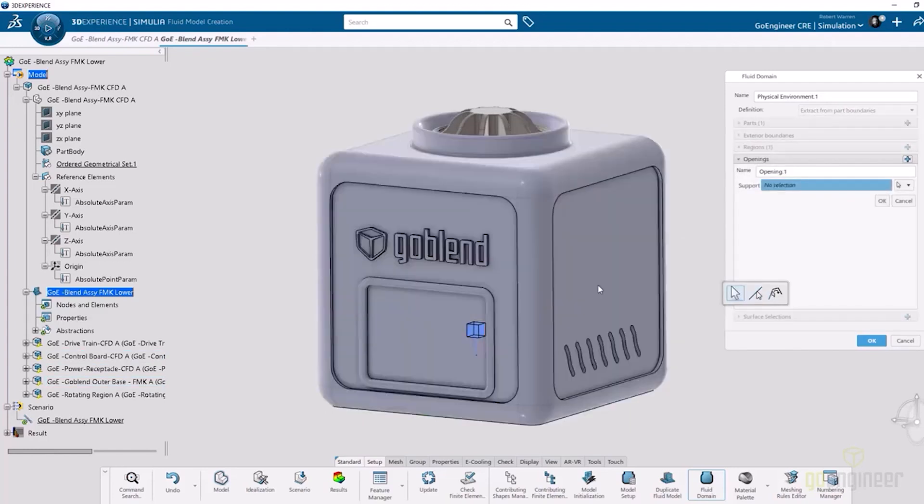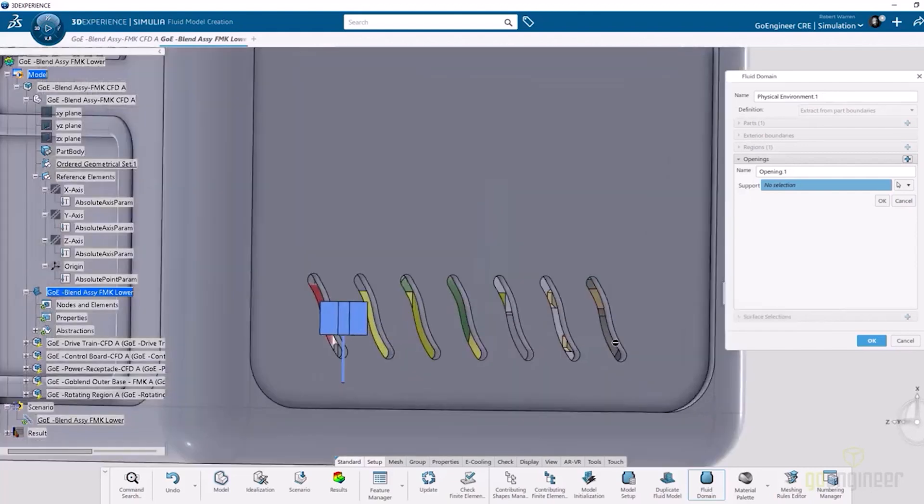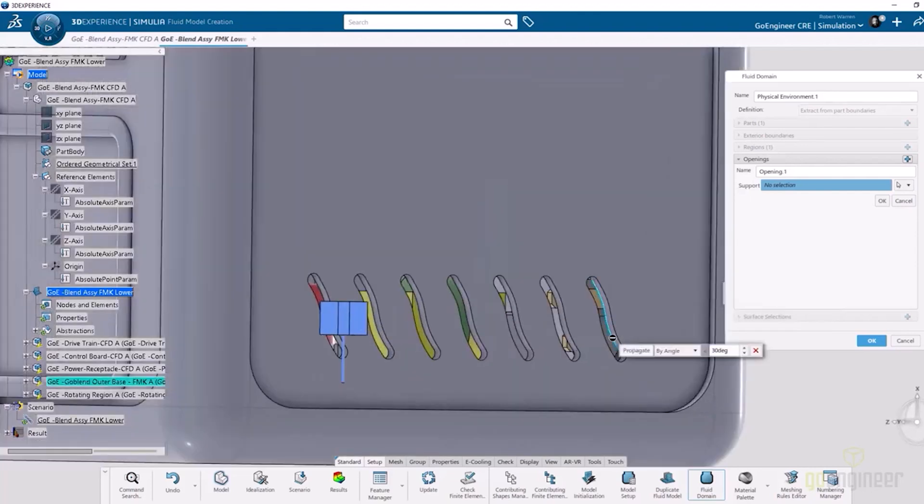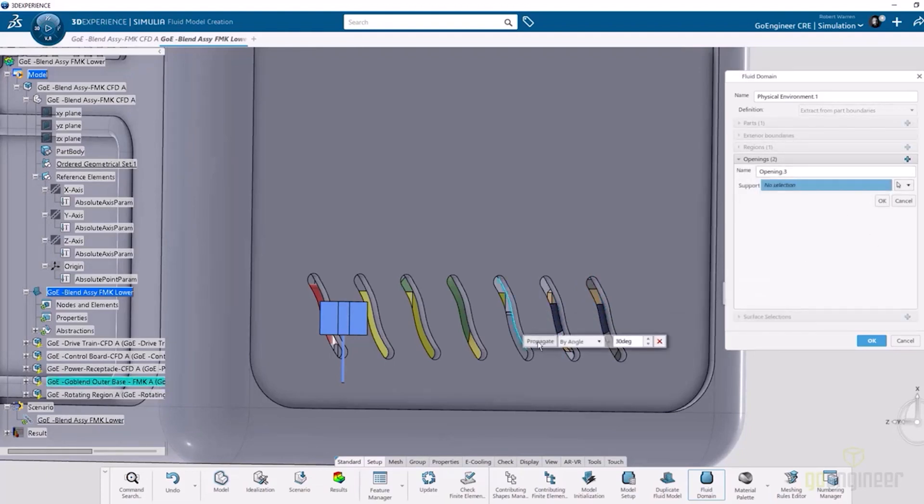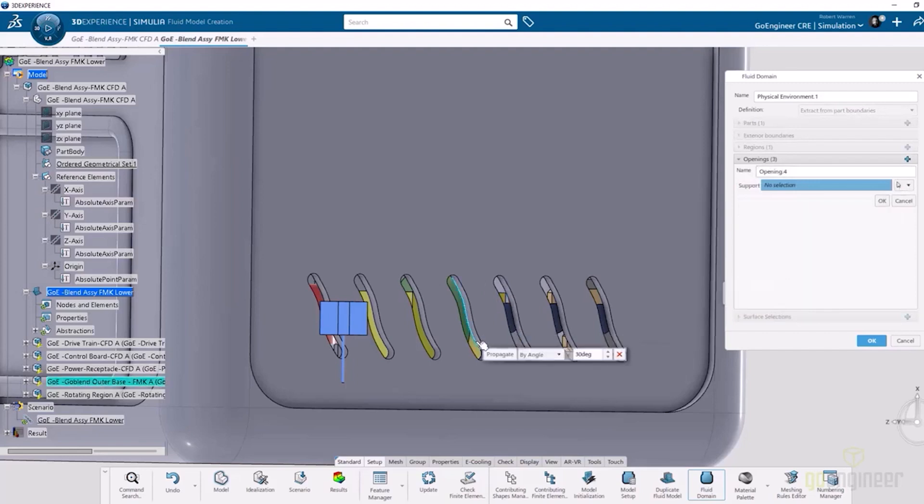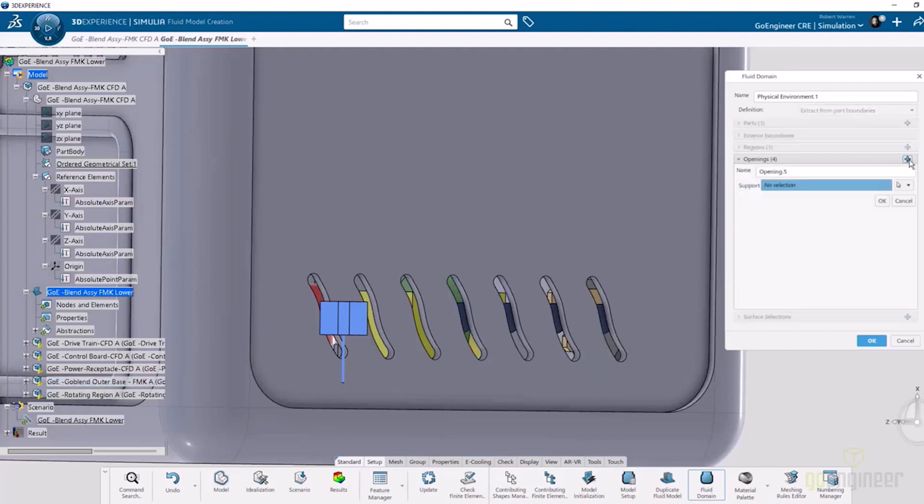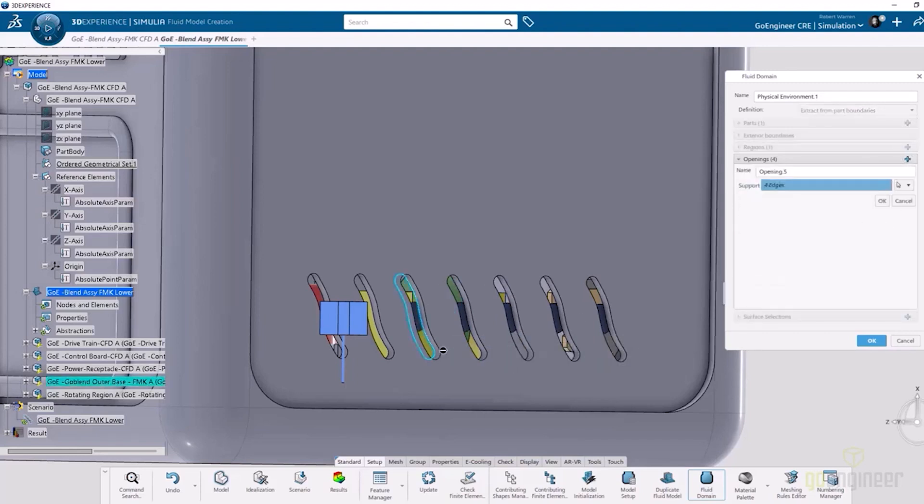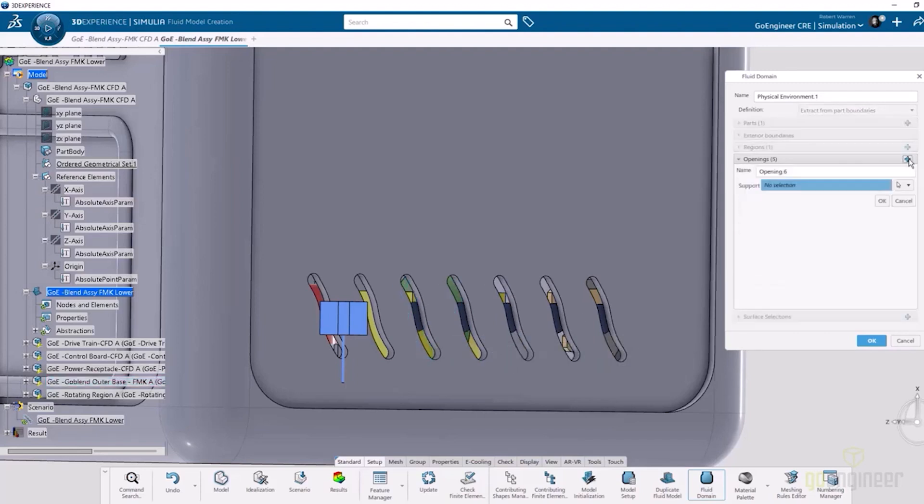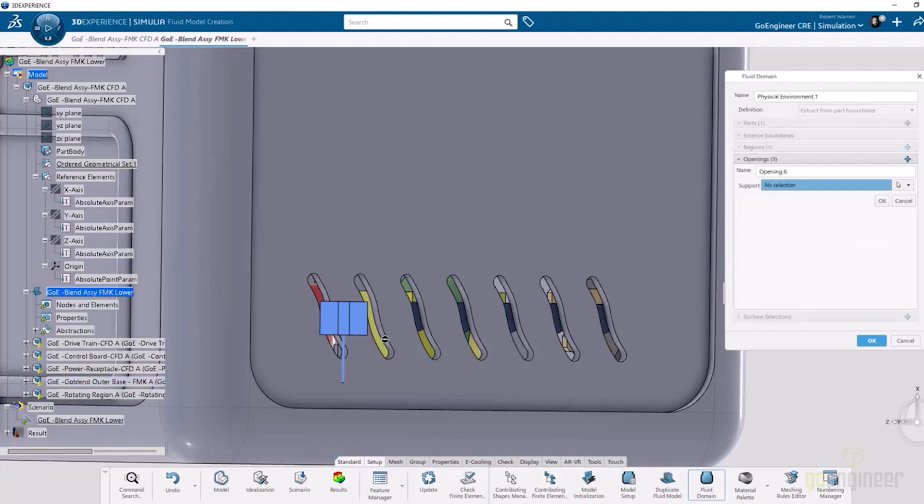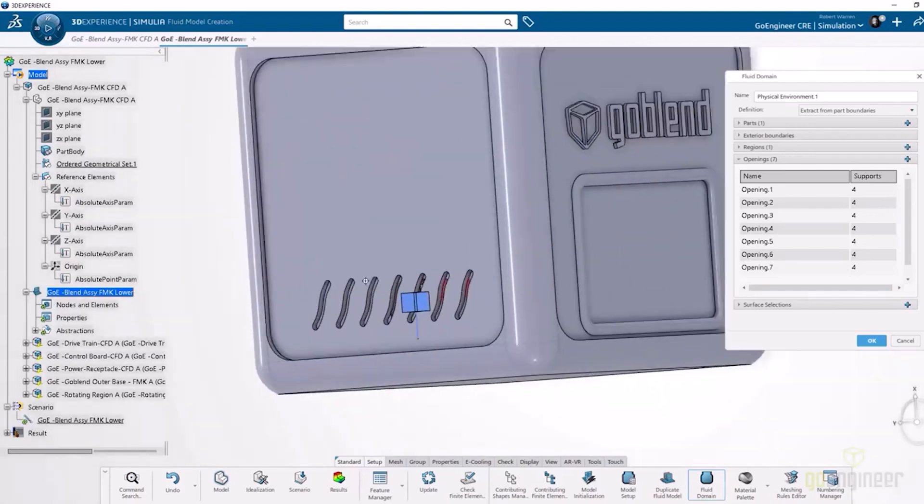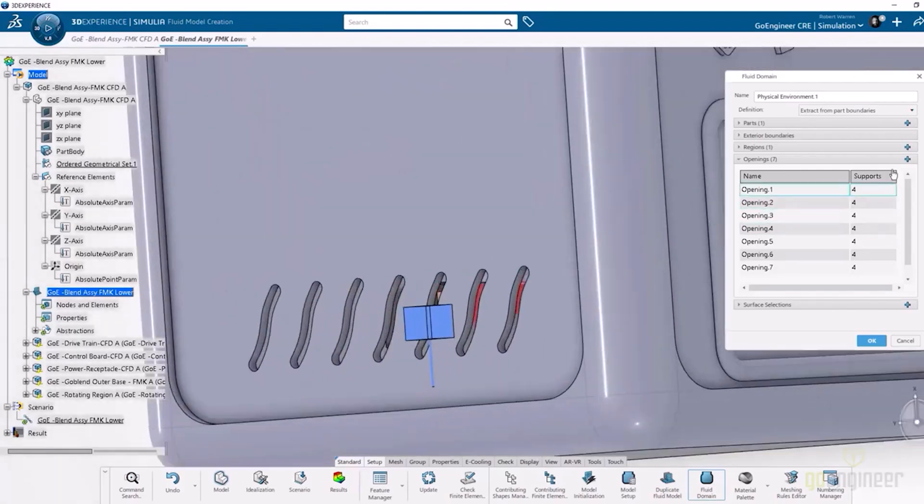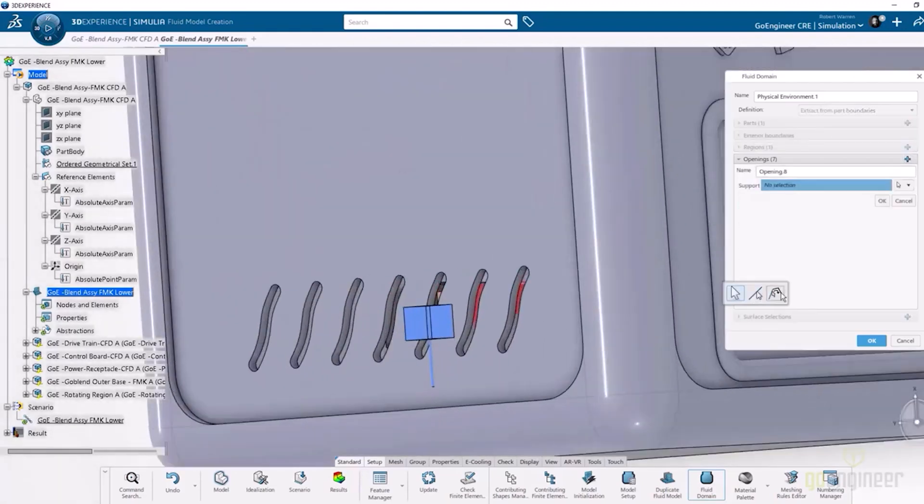Then I can select my openings. I'm showing you the setup on the lower vents only, but we'll look at results for all three. I'm specifying my openings, so we can populate automatically the edges of the openings and specify that as a boundary condition face. You can see that with the blue disc behind the scenes there. We're going to do the same thing on the opposite side for the vents.